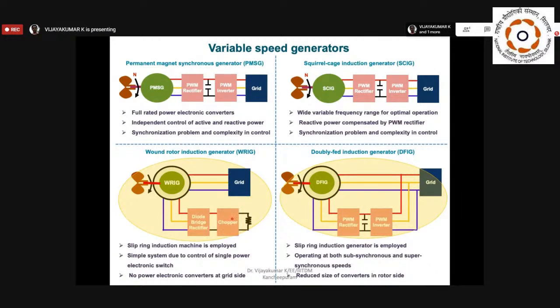By varying the duty ratio of the chopper, you can vary the rotor equivalent resistance. Once you change the rotor equivalent resistance, you can control the speed of the generator. So by controlling the rotor equivalent resistance value, you are controlling the speed of the generator. Here there is only one switch, and the control is very easy.